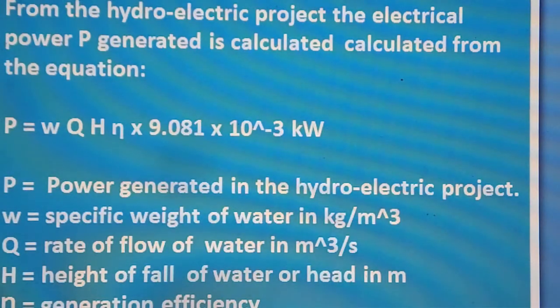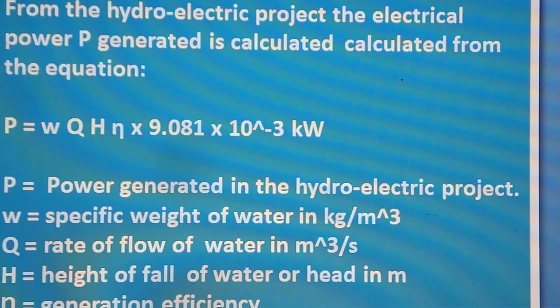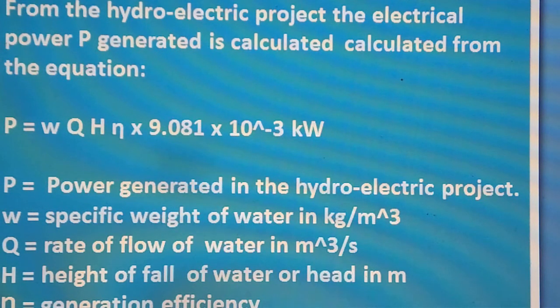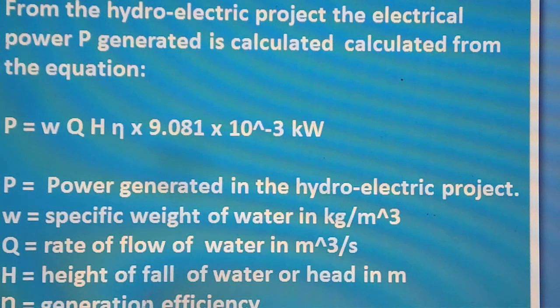To remember: P = w·q·h·η × 9.081 × 10⁻³ kilowatts. We can also convert this into kilowatt-hours as a unit of electricity. In the next class, we will have a numerical problem related to this power generated. P is power in kilowatts; w is specific weight of water in kilograms per cubic meter; q is rate of flow in cubic meters per second; h is height of fall or head in meters; and η is generation efficiency.